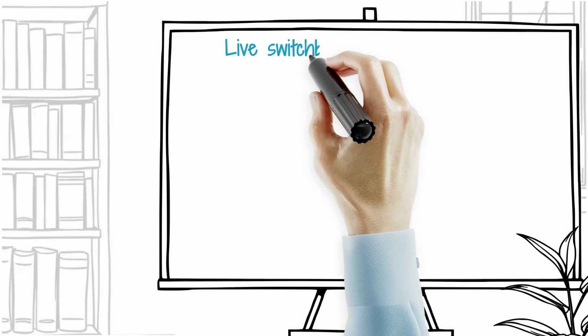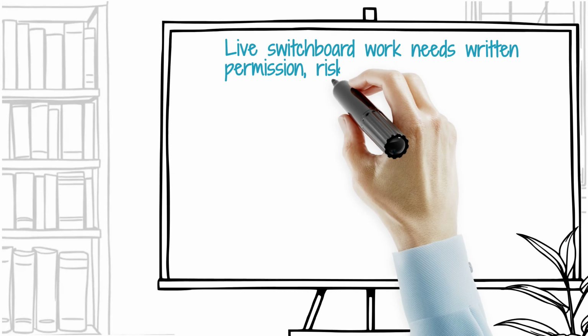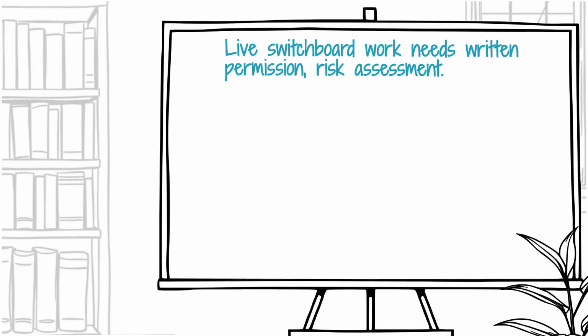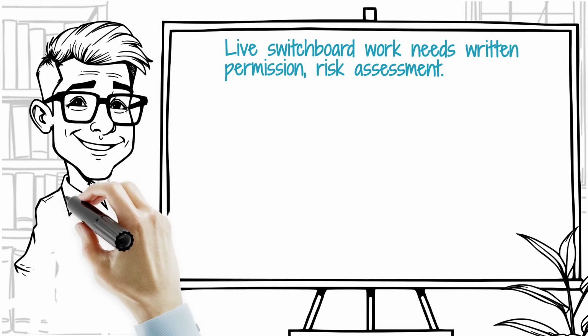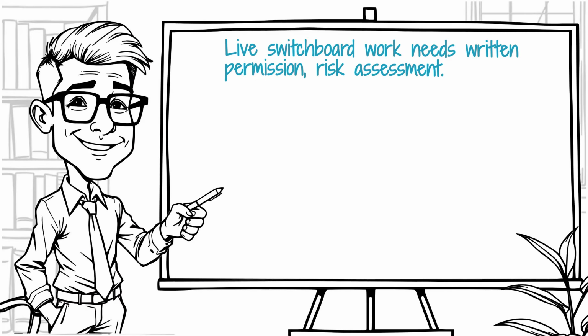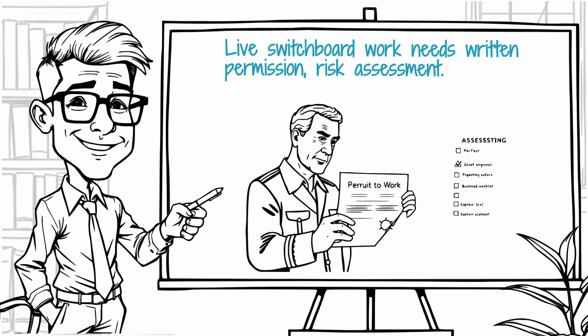Work on a live switchboard must only be undertaken as a last resort when isolation is impossible and the ship's safety or mission integrity is immediately at risk. This work requires written permission from the chief engineer or master, following a documented, detailed risk assessment and a formal permit-to-work system.